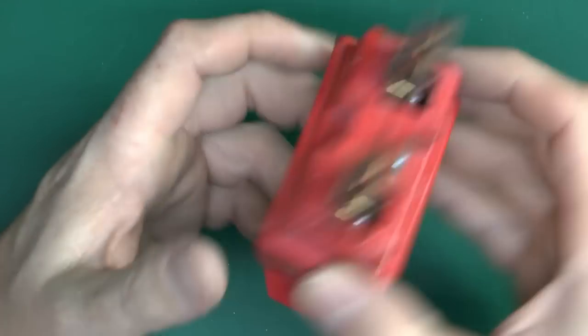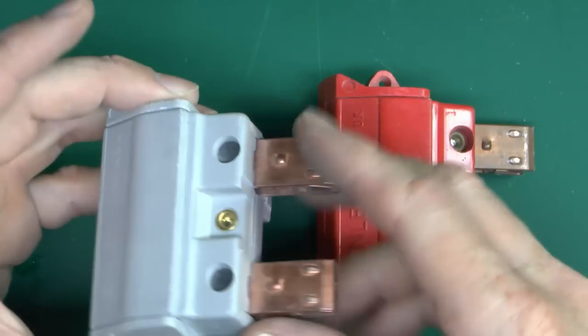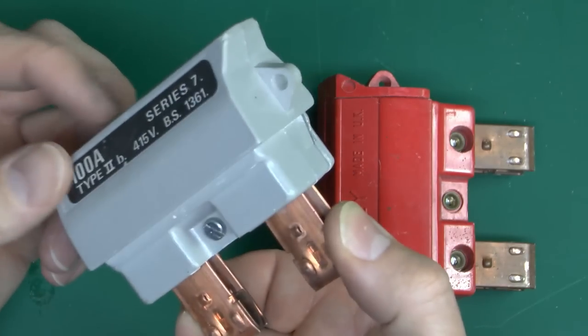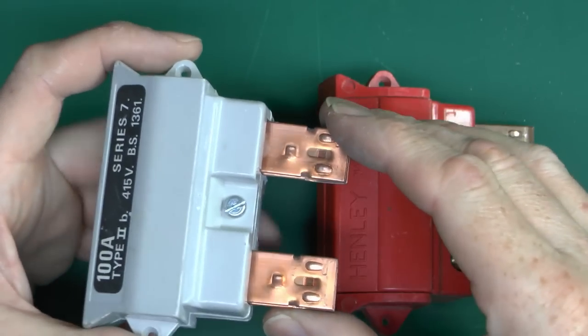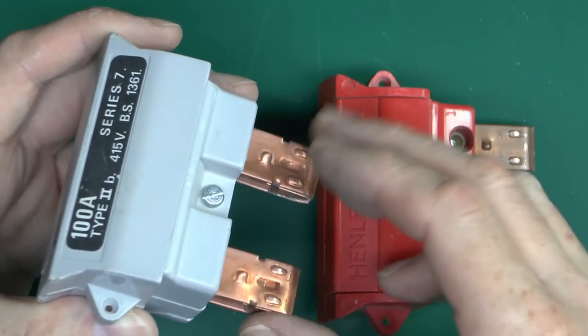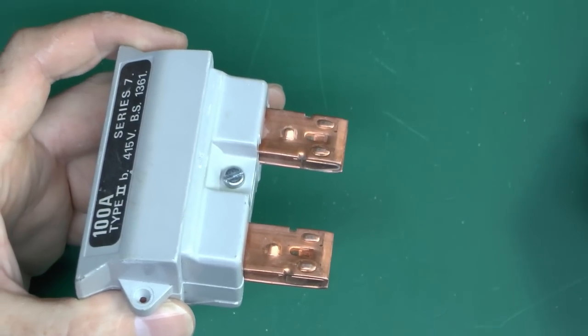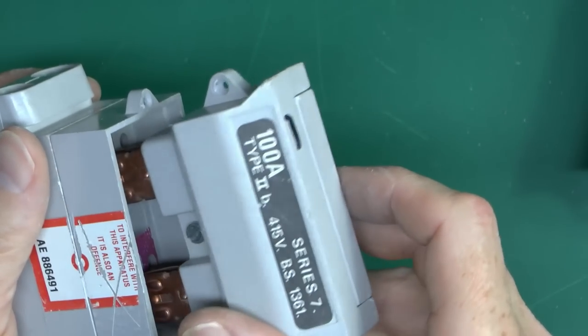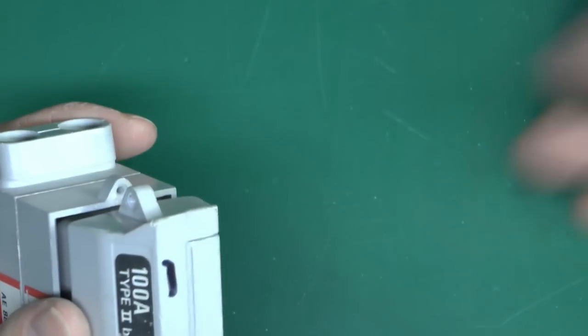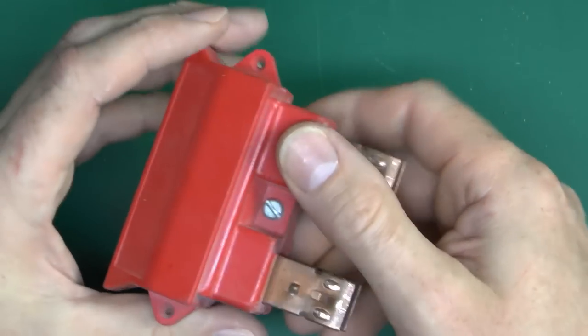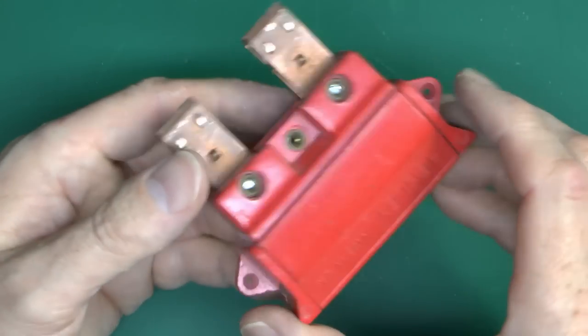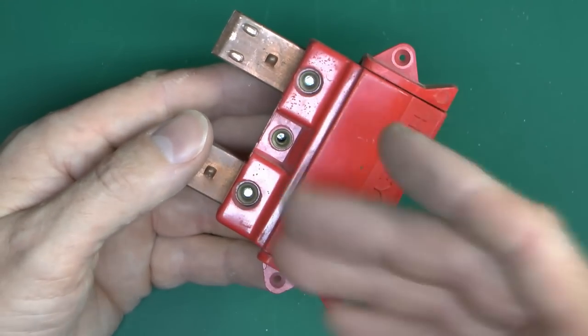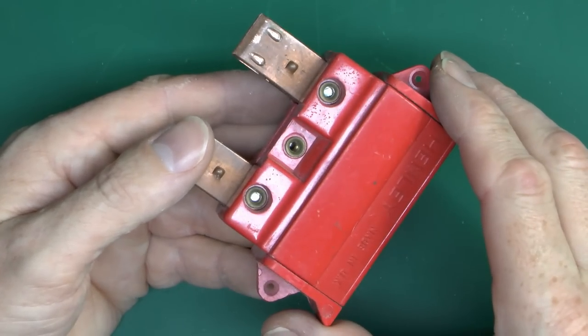The reason these are used is in a block of flats. So you may have this in the basement or some kind of room where all the stuff comes in. So that's your actual fuse. But you may have the actual meters in the individual flats. Of course it's not appropriate for the meter operator or whoever to install the meter upstairs, have to go all the way downstairs to some distant switchroom and remove this, and then go upstairs and hope that they got the right one, and also hope that nobody sticks this back in while they're working. So what's done is that you have all of these in a basement room, which is the actual fuse, cable from here going up to your individual flat, and then in the flat you have this style. So this would be used purely for disconnection of the supply when you want to change the meter or whatever. No fuse here because the fuse is then in the other one downstairs in the intake room.